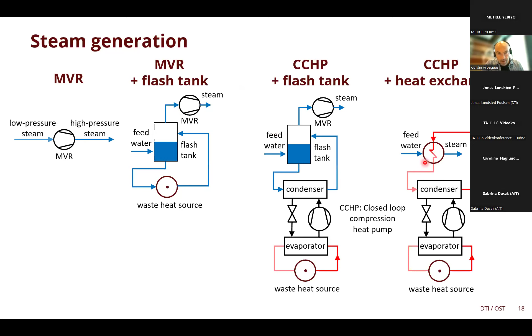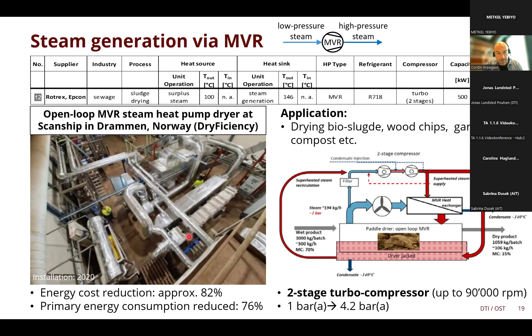So this case is also a demonstration site developed in the DryFiciency project. It's at Scanship in Drammen in Norway for biosludge drying. And this demonstrator is an open loop MVR system and uses a two-stage turbo compressor with speeds up to 90,000 RPM. So steam from the dryer is recompressed from 1 bar to 4.2 bar, and this gives a pressure ratio of up to 2.1 per stage. The demonstrator achieves a capacity of 500 kilowatt, and as an acceptance test, 50 tons of garden waste was dried in this demo.